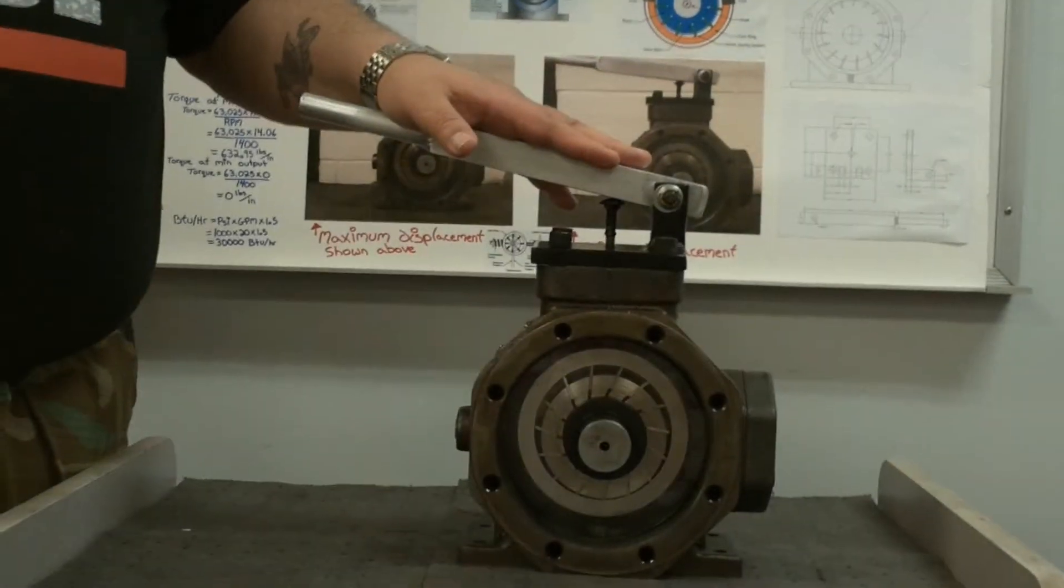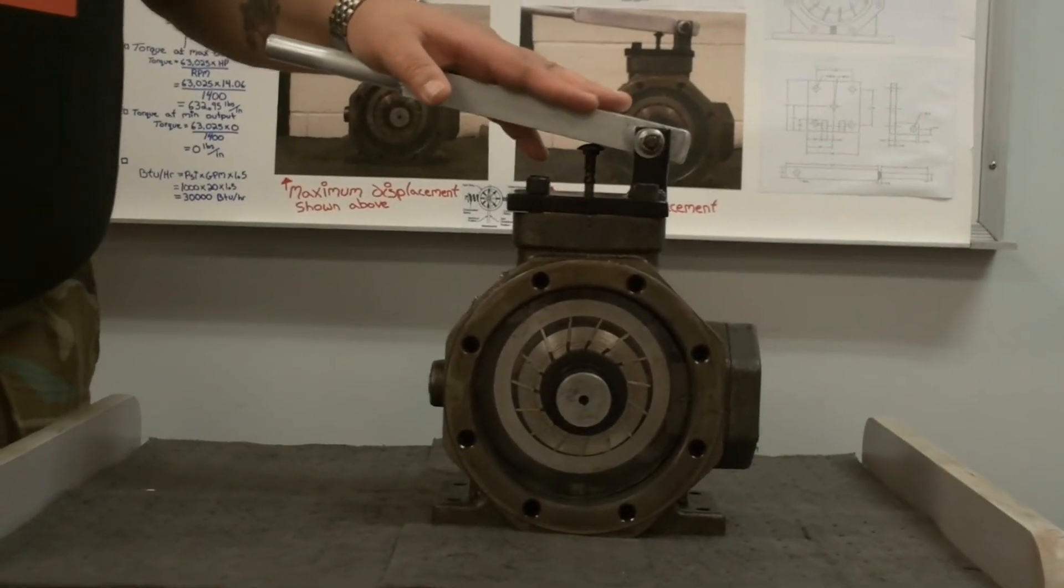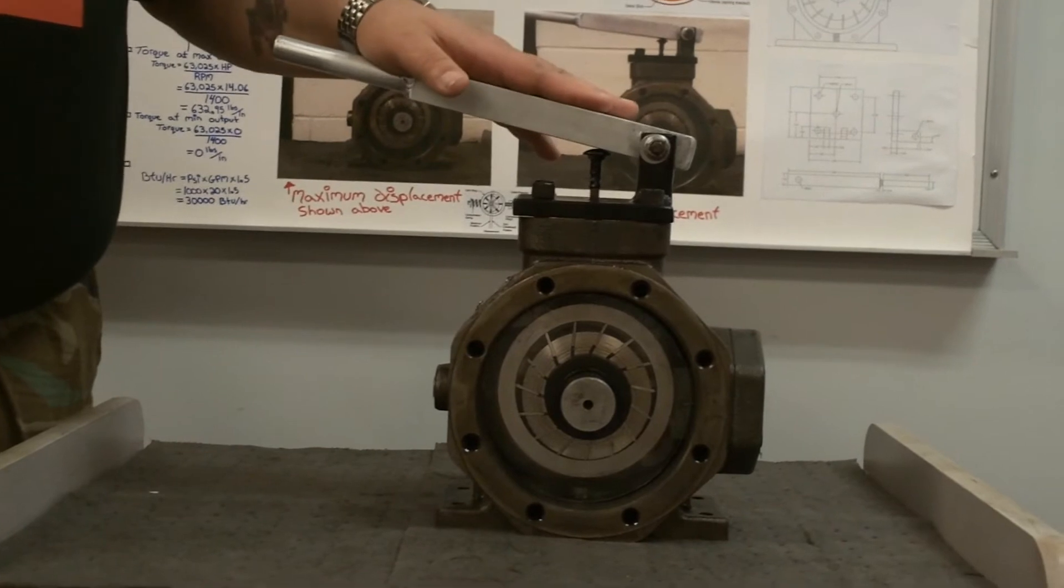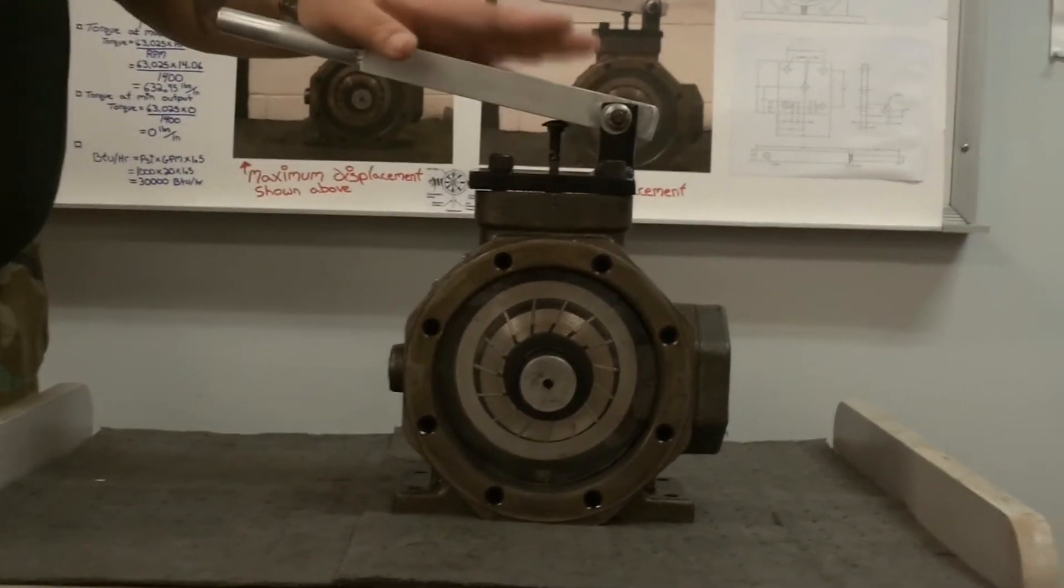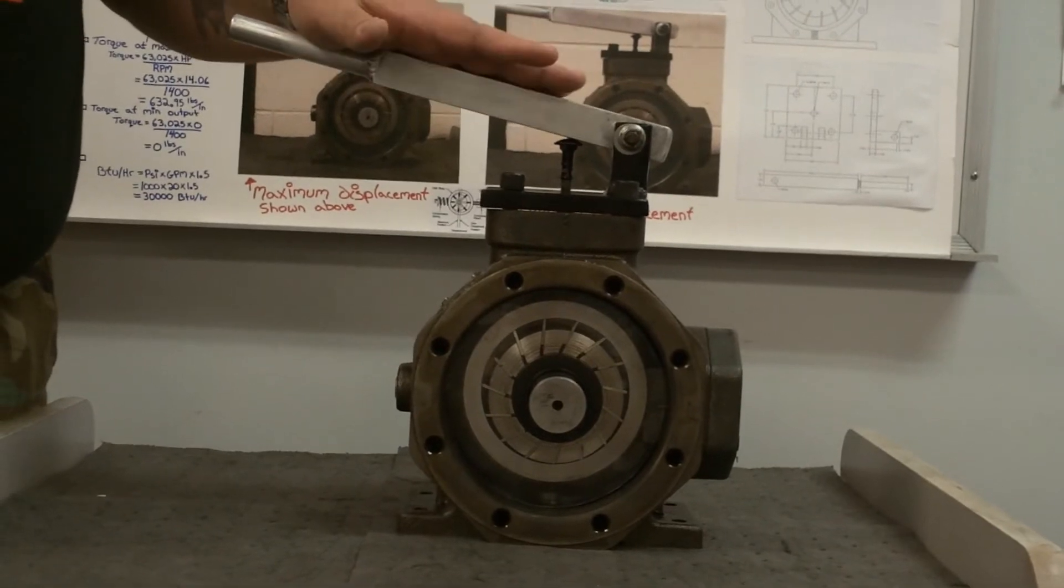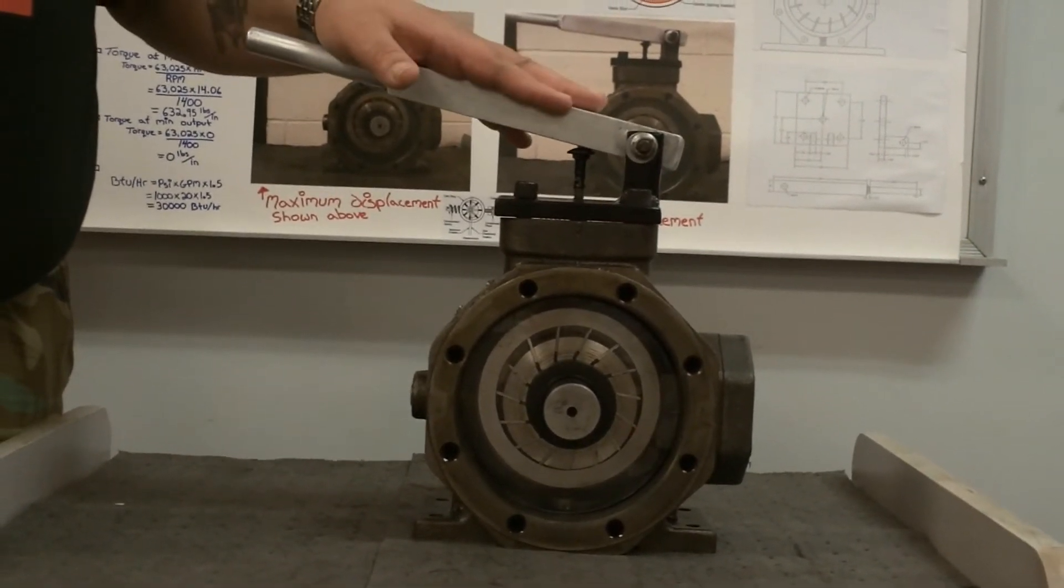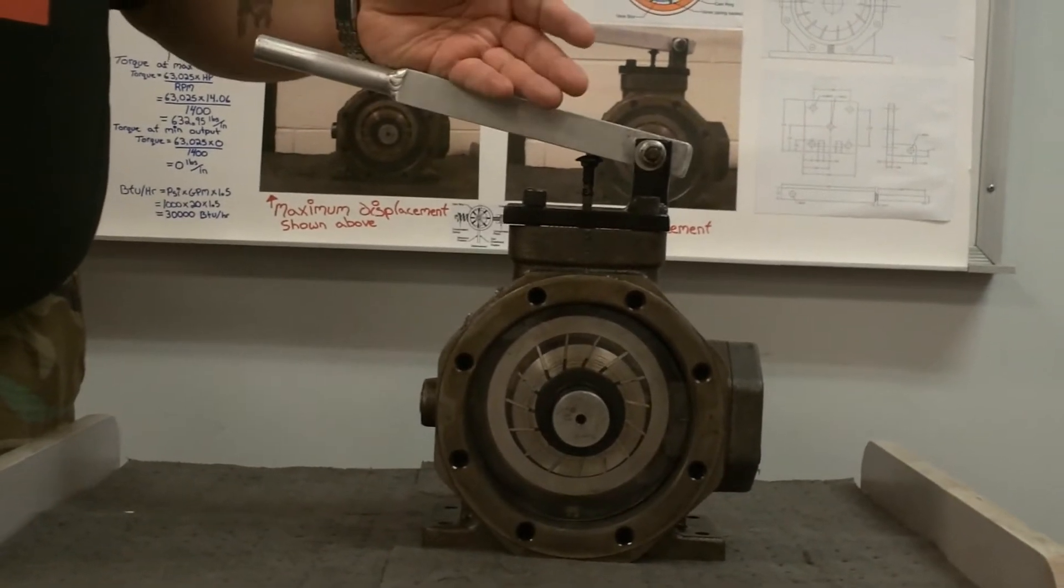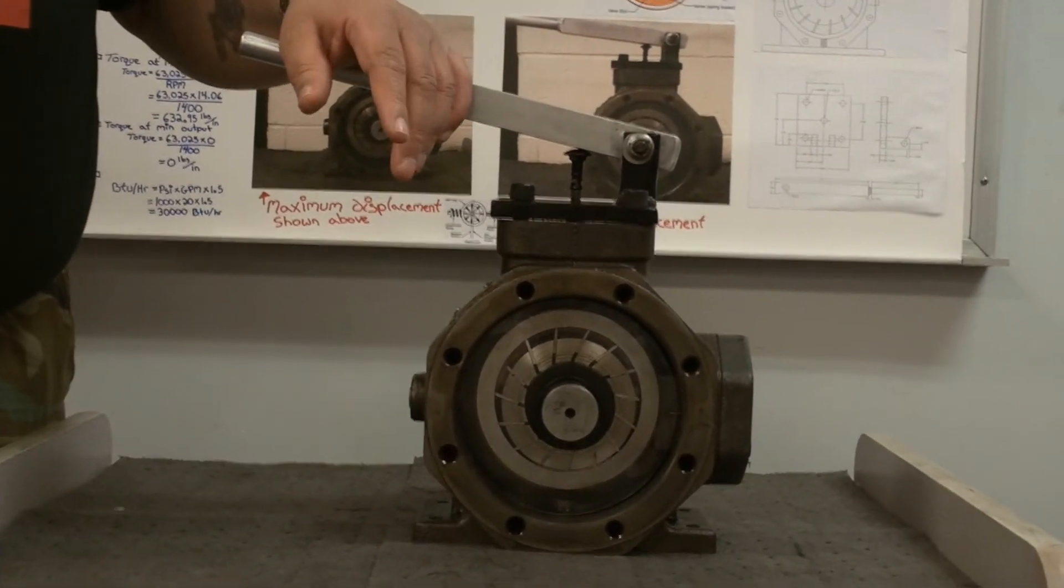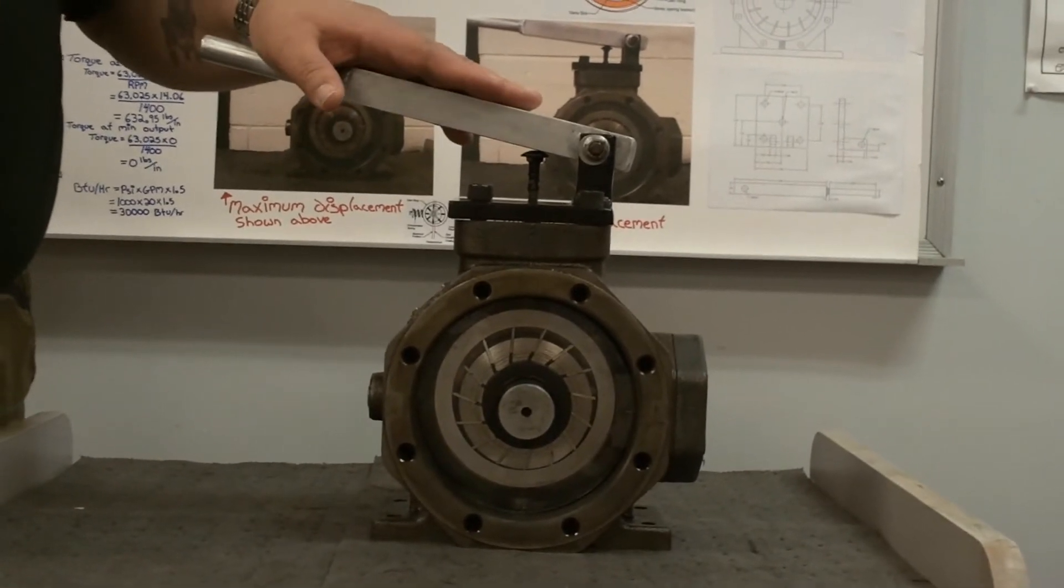All right, this is a variable displacement hydraulic pump used in a variety of applications. It's much more efficient than a fixed displacement pump. A fixed displacement pump requires a large motor to handle its maximum flow rate at all times. Any excess oil isn't generating work, it just goes back to the tank. It can cause some problems with heat and it's definitely not as efficient.